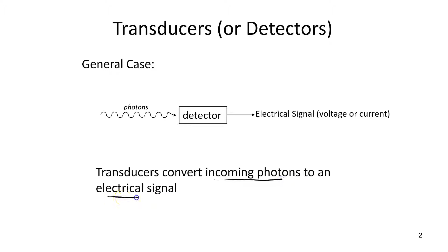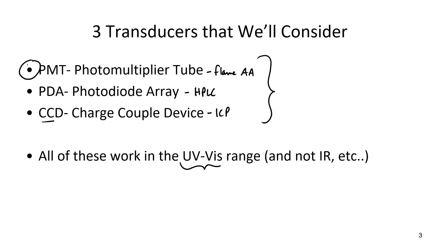We will talk about three different transducers: the photomultiplier tube, the photodiode array, and the charge couple device. If you're taking the lab, I want to say that the PMT was in probably the flame AA. You didn't use any instruments that had a PDA, but we do have an HPLC that has a PDA, and if you use the ICP, it had a charge couple device. All three of these transducers only work in the ultraviolet visible range, and in this video, we'll focus on the PMT, the photomultiplier tube.